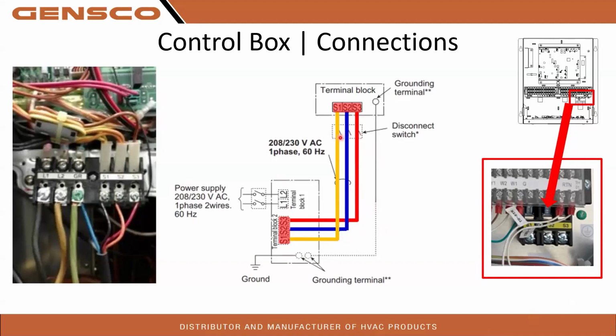If you do require a disconnect switch, be it on a commercial job or local code, make sure you use a 3-pole disconnect. If you use a 2-pole disconnect, then your S3 or whatever one's not connected will still have 120 volts to ground. So always make sure to use a 3-pole disconnect and don't trust the electrician that they did it right. If you're doing maintenance or service work on a job that has a disconnect and you flip that disconnect, always check voltage to ground. I see it a lot where electricians will only put in 2-pole disconnects and you still have one hot leg. And that can be a real bad day real quick for you.